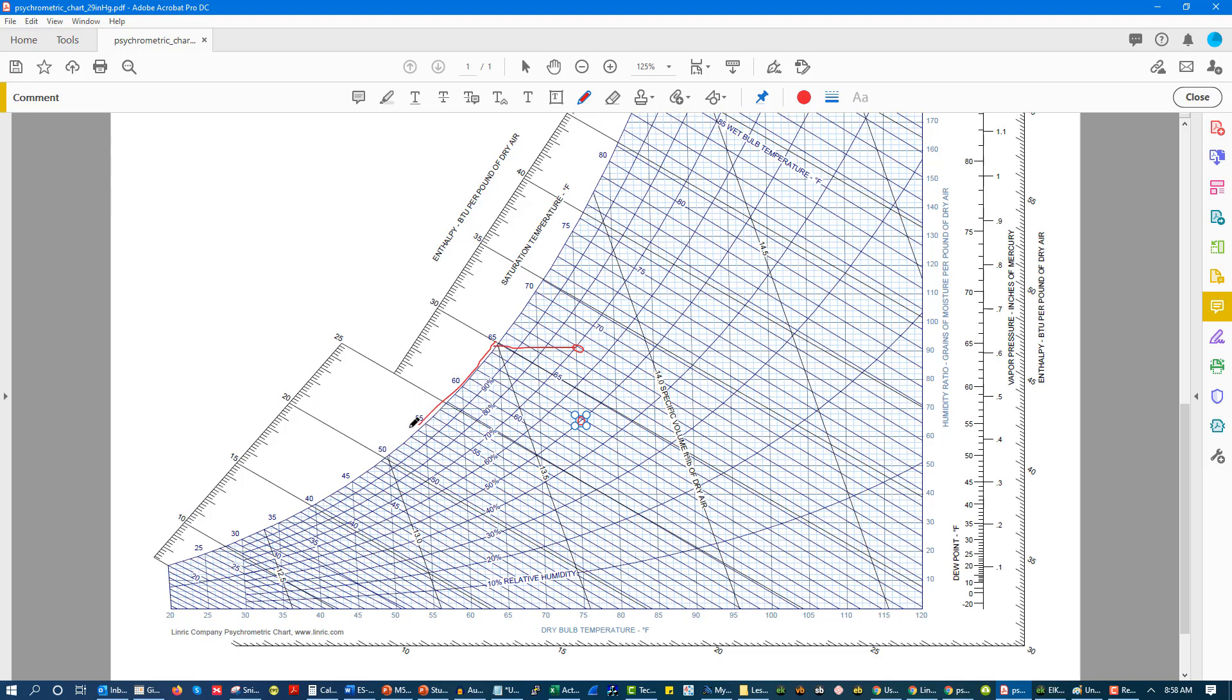And this is why 55 degrees is a set point for most air handling units, by the way, because we're coming in at 75 degrees and we've got that 10 degree delta, right? See, 65, 55. I hope you're starting to see this because oftentimes you're like, why do I have a 10 or 12 degree delta on my coil, entering and leaving?